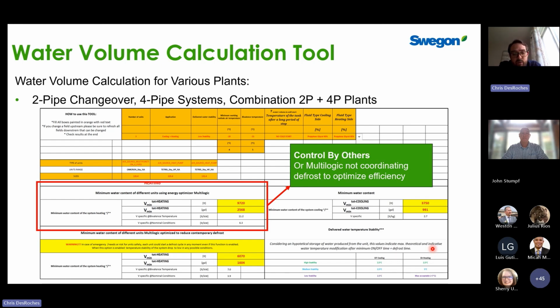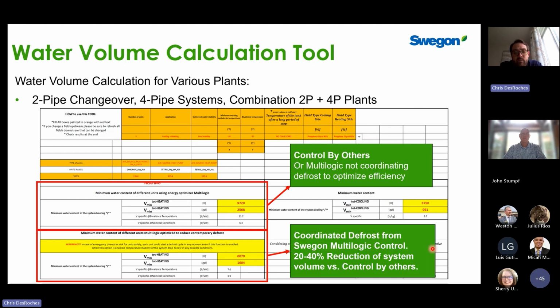We talked about last time how we can coordinate defrost of multiple units, similar to what we saw in that example with 4 units, all defrosting at the same time. Swegon's controls prevent that to mitigate it as much as possible. If it's controls by others, though, you can't prevent every single circuit from defrosting at the same time because it's a safety function at the end of the day. So we'll provide that value, and then we also provide a value whenever you're using our controls to optimize and reduce defrost. Generally, we're able to reduce the volume by about 20 to 40% because the likelihood of multiple circuits all defrosting at the same time has been mitigated.